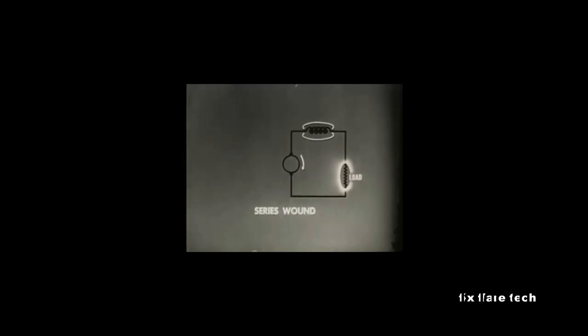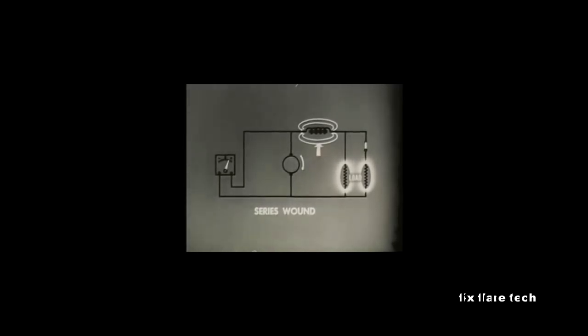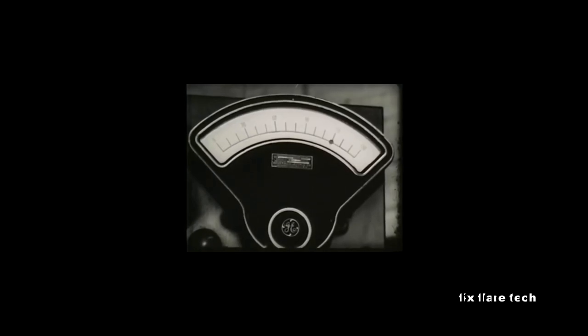The field coil winding may be connected in several ways. This is a series-wound generator, which means the field coil is in series with the armature. Because of this series arrangement, it has poor voltage regulation. Additional load will cause more current to flow in the field coil, increasing field strength and thus increasing voltage. This continuing action stops only when the core is saturated. When the load is increased, the voltage will increase; when the load decreases, voltage will decrease. Voltage regulation in the series-wound generator, therefore, is very poor.